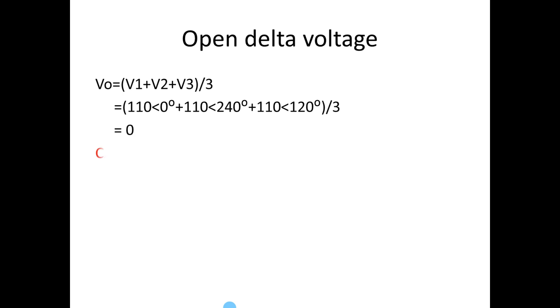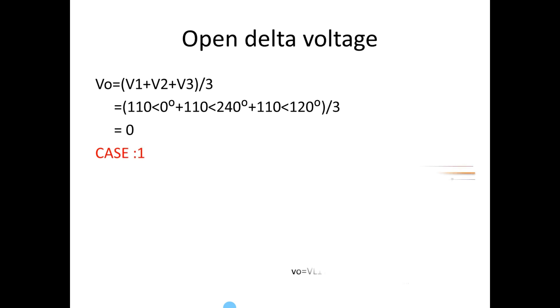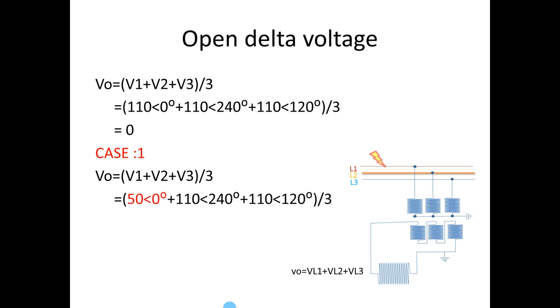Now we are going to see some case studies. Case 1: let us consider a fault on R phase. During this time, depending upon the fault current, the R phase voltage will be dropped. Let us consider the voltage on R phase is 50V, with remaining phases at 110V. The open delta voltage we get is 20V at 180 degrees.